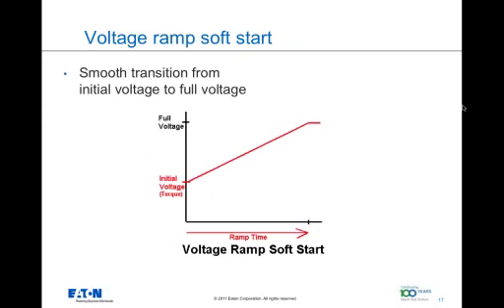This graph shows the voltage ramp as provided by soft starters. Soft starters provide the smoothest transition from initial voltage to full voltage, as shown in this picture. It is a linear ramp going from an initial voltage setting, as dictated by the customer, to the full voltage over a period of the ramp time.